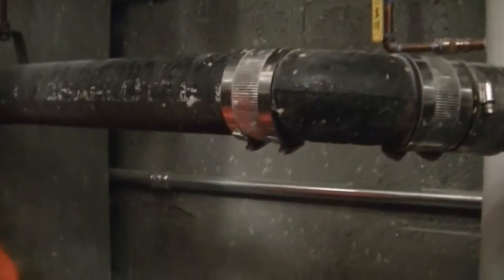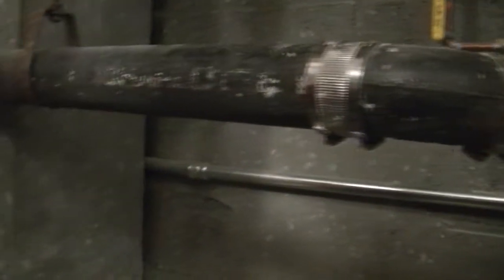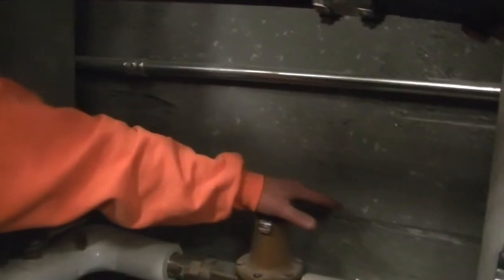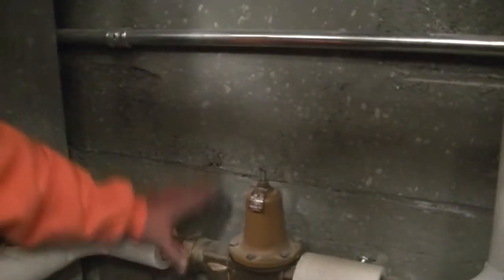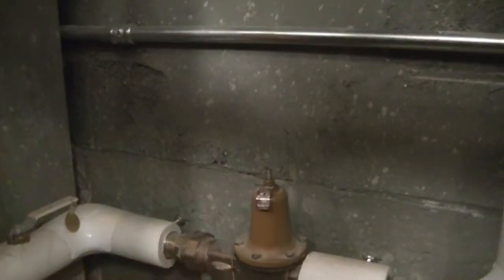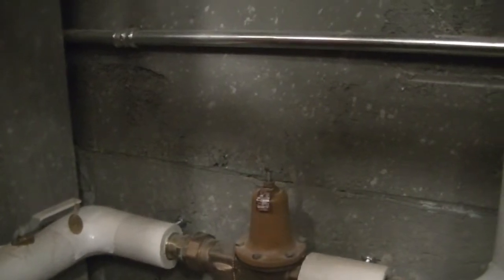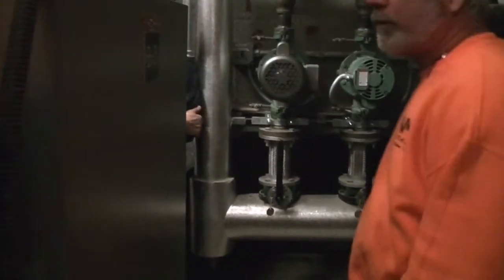Okay, if you wanted to reset this, you would go to the top of the system where it bleeds in, isolate that, bleed some pressure off, and then reset the spring in it. These do go bad over the course of time. It takes a long time, but they do go bad. It's not uncommon. If it does, you have isolation valves on both sides. There's a union. You can spin this off, okay, and replace it if need be. Any questions down here so far? No? All right, I'm going to show you. Before we go up, go ahead.